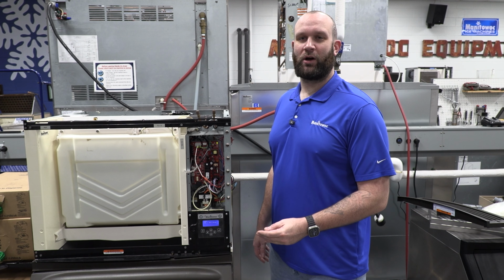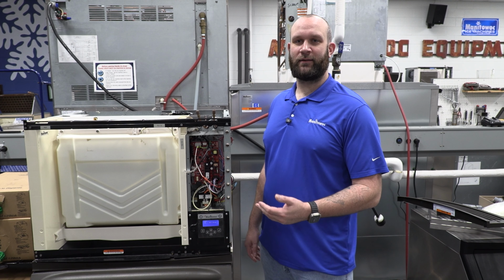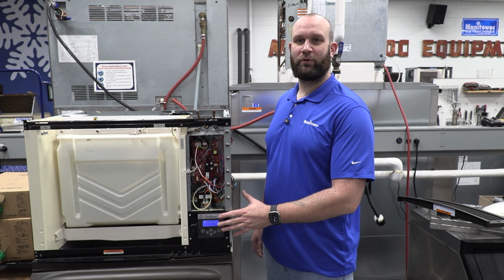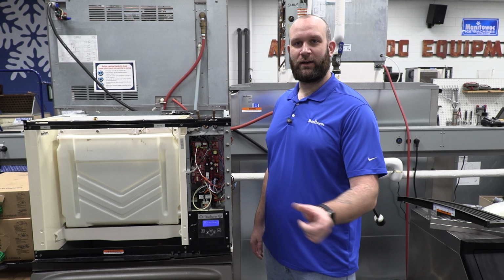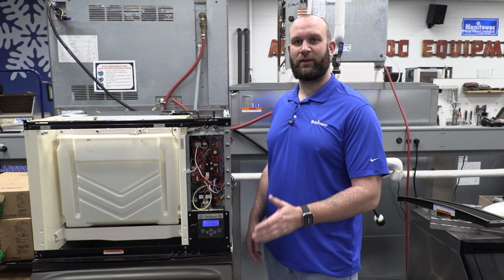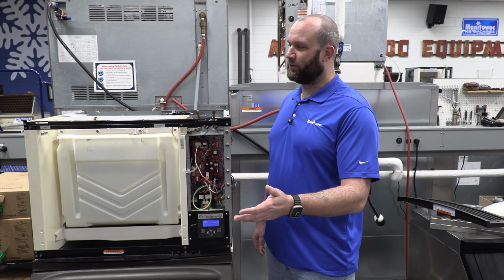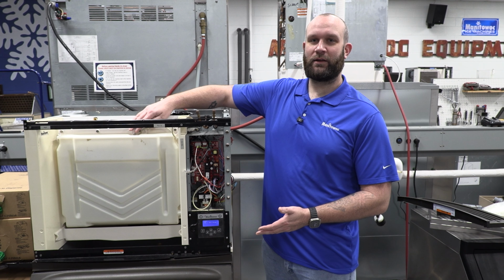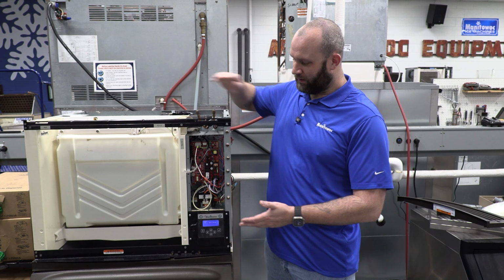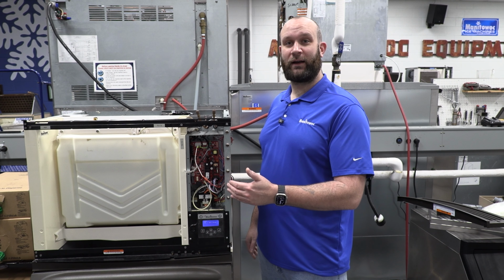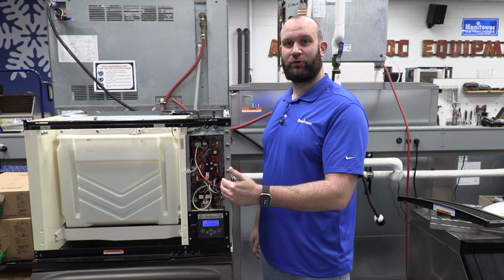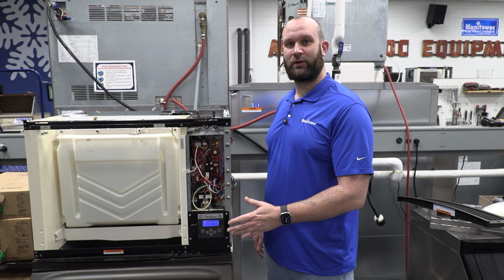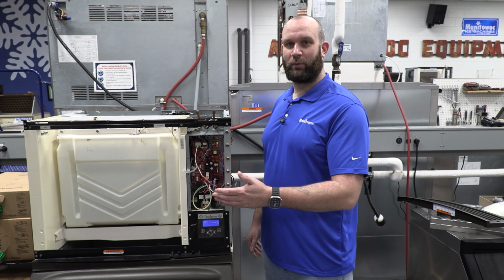And usually when we get this call in tech support, the complaint is the machine goes right from pre-chill into harvest. It never actually goes into a freeze mode. Usually it's accompanied with a note that says the tech in the field already changed the ice thickness probe. Sometimes I've even seen them say that the tech has changed the ice thickness probe and the control board. Today I'm going to show you how to determine the actual root cause of why this is happening.